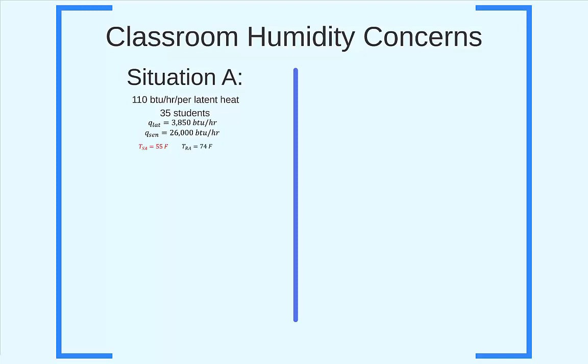Assuming a room air temperature set point of 74 degrees Fahrenheit, we can calculate the airflow that would need to be coming into the space to meet the sensible load. So this system would be putting in 1244 CFM into the space. What relative humidity would the space balance out at?